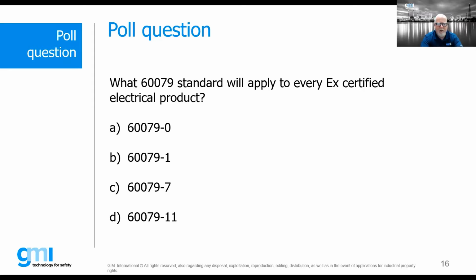It'll also reference -11 for intrinsic safety, but it'll also probably reference -15, which is for non-sparking or non-arcing, and then also probably the dust standards. So you're going to see a bunch of different standards referenced on a particular certificate, but -0 is going to show up pretty much everywhere.